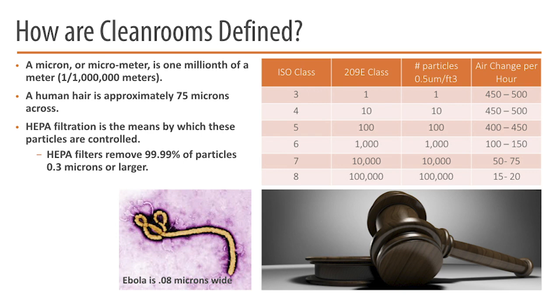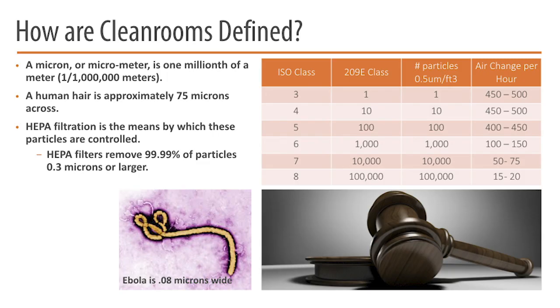Just to give you some context, a micron is a millionth of a meter. A human hair is about 75 microns across. So we're talking tiny, tiny. Even though the width of Ebola is less than that, the overall length is such that it's going to get caught in a HEPA filter. A HEPA filter, high efficiency particulate arrestor, is a pleated type of filter. That's what's located at the ceiling level of these clean rooms, with either a central station air handling fan pushing air through it, or individual fans coupled to every filter. And HEPA filters are going to pull out 99.99% of particles 0.3 microns and larger. So we're talking very small levels, but depending on what you're working on, those particulates at that level can really mess up your operations.